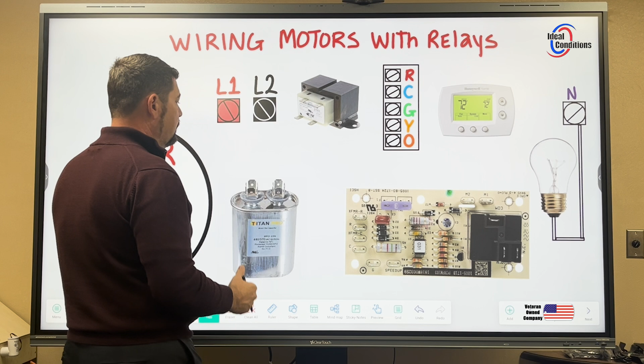Where else does L2 need to go? Well, L2 needs to get over here. But before it gets over here to my motor, it needs to come over to the relay that's on the board. And if you see here, it's upside down. Okay, but this is common, normally open, normally closed. So what I'm going to do is obviously wire to my normally open, because we've already demonstrated that normally closed will always have power between common and normally closed in this state.